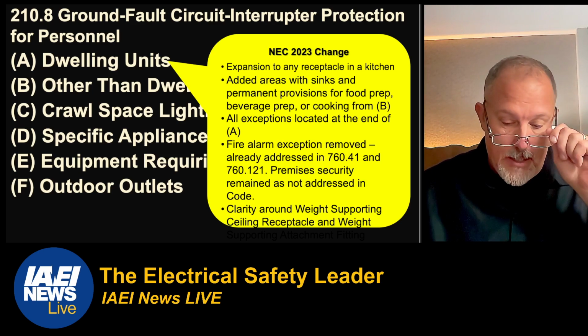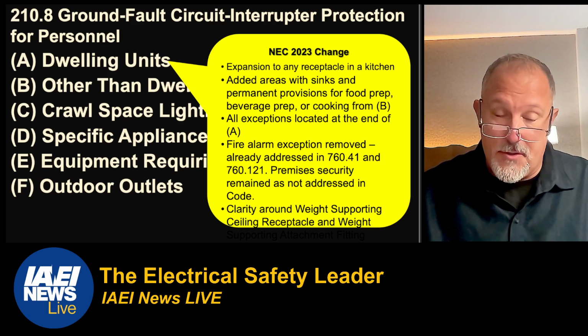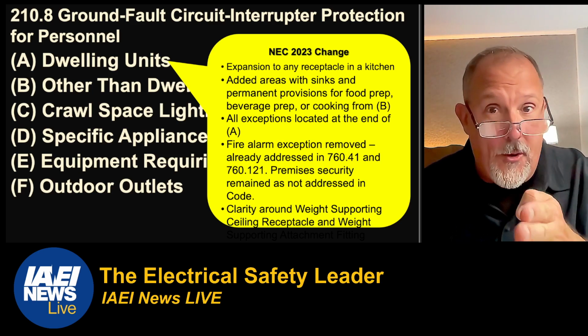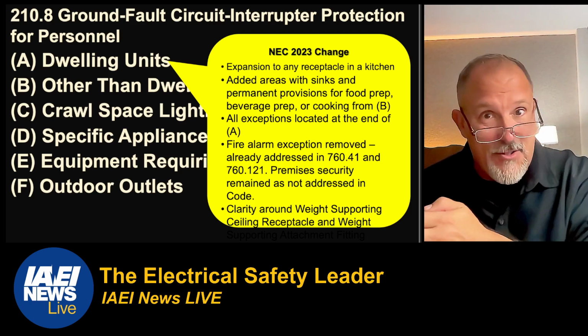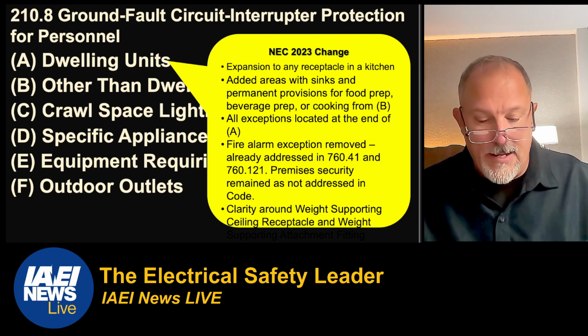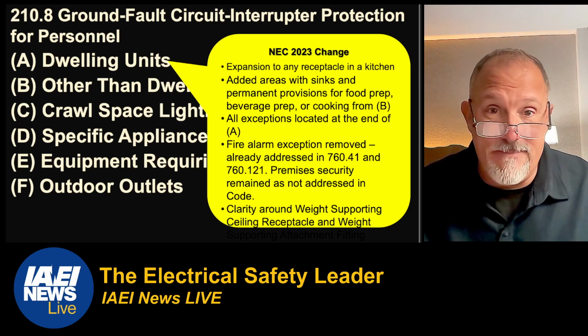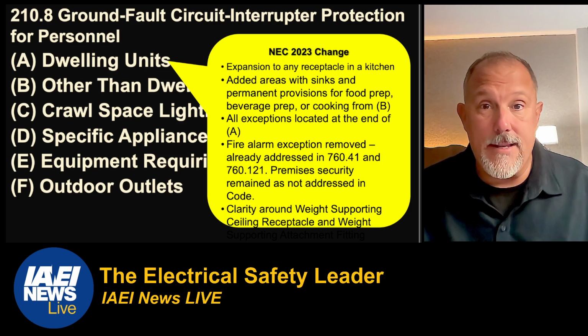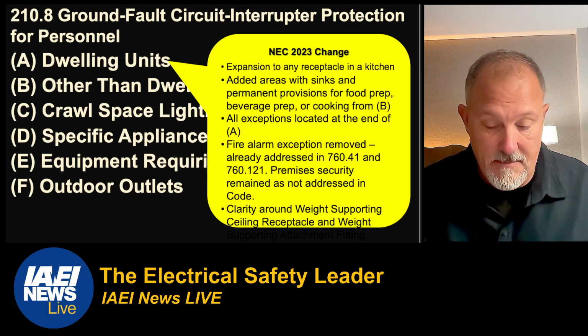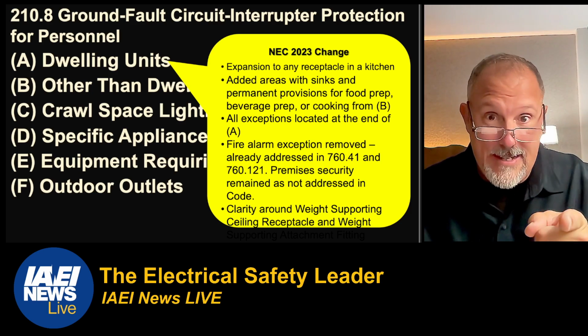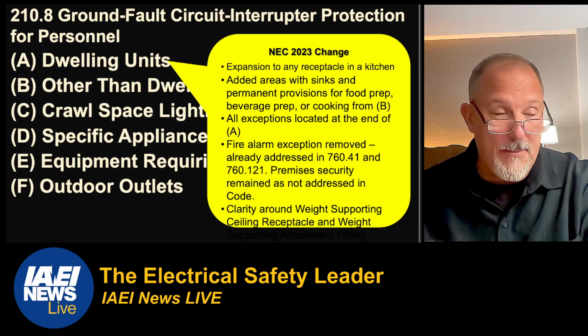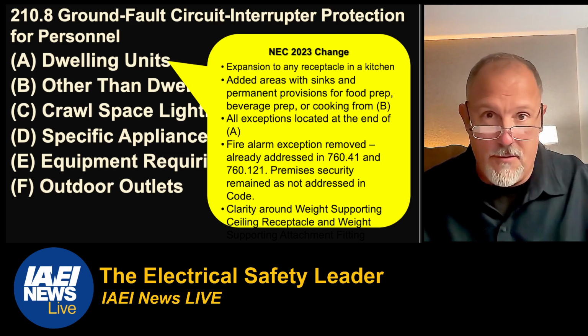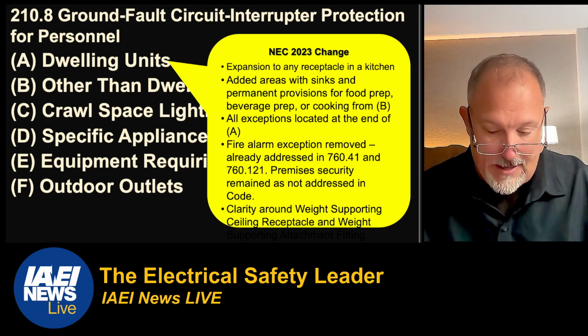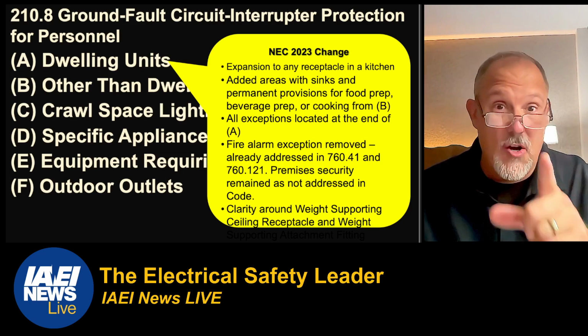Well, somebody said, well, what's good for the goose is good for the gander. Does the electron know that it's not in a dwelling unit if I have an area like that? And the electrons, I hate to break it to you, they're not that smart. So they're lazy and they always love to party. So any place where there's a fault, they just love to go there and they find the shortest paths. So in any case, they take all paths.